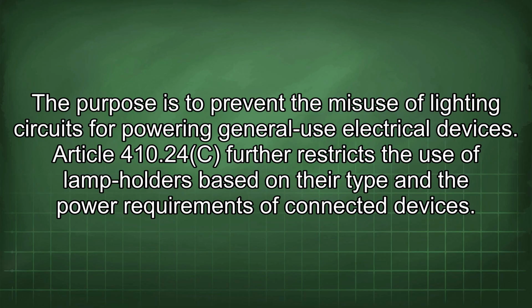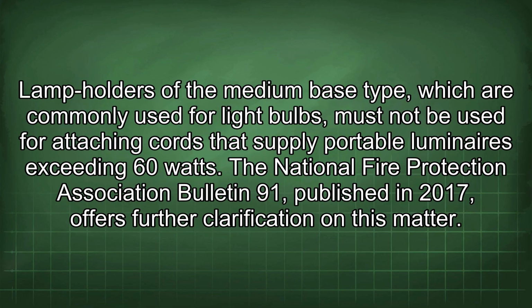Article 410.24(C) further restricts the use of lampholders based on their type and the power requirements of connected devices. Lampholders of the medium-base type, which are commonly used for light bulbs, must not be used for attaching cords that supply portable luminaires exceeding 60 watts.